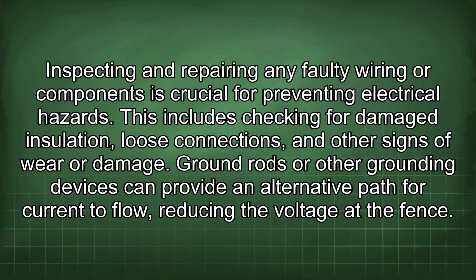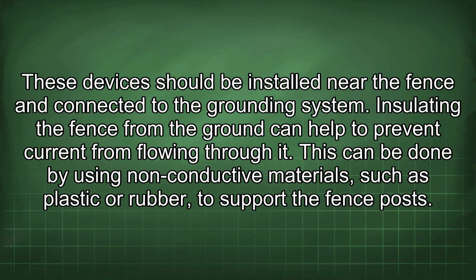Ground rods or other grounding devices can provide an alternative path for current to flow, reducing the voltage at the fence. These devices should be installed near the fence and connected to the grounding system. Insulating the fence from the ground can help to prevent current from flowing through it. This can be done by using non-conductive materials such as plastic or rubber to support the fence posts.